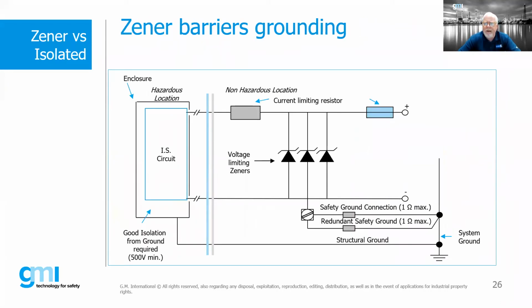So here's our Zener barrier grounding. This is also something that many people will actually do. You'll notice in this case we have two ground connections: our safety ground connection and our redundant safety ground. Now, it is actually a requirement that we periodically check the resistance of our ground. Well, the moment that we remove one of these ground legs to check the resistance, we now have a potentially dangerous situation.